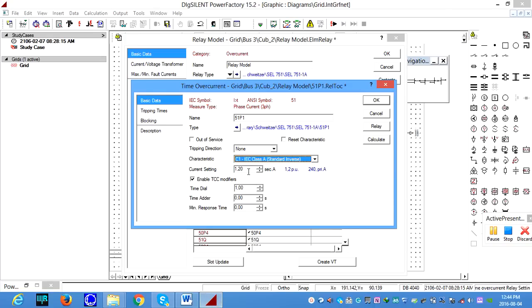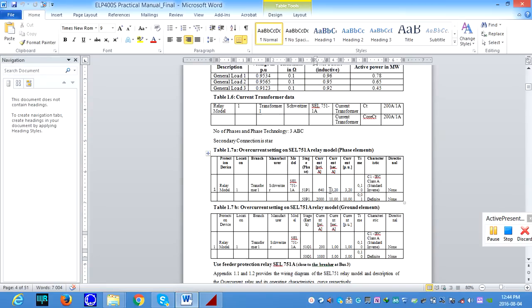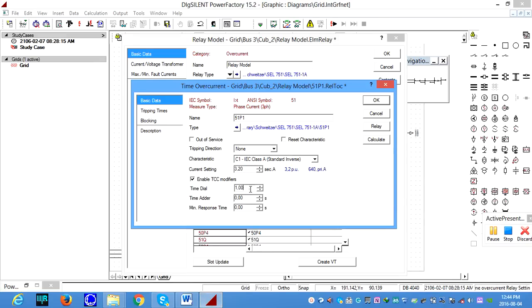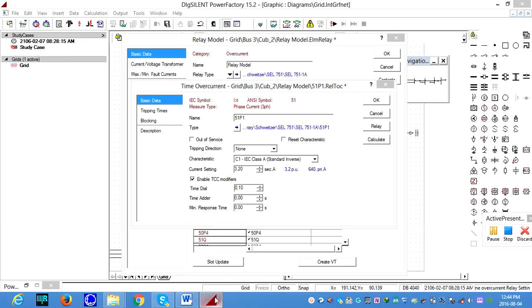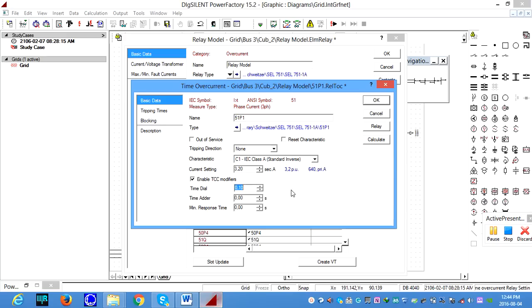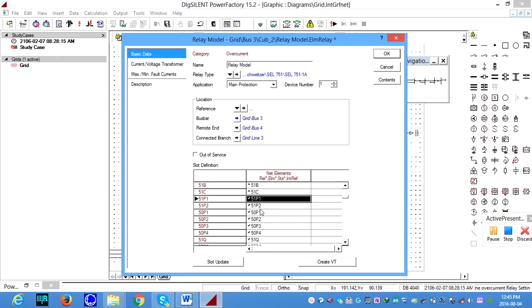Okay, and the time setting, we need to make sure of the time dial and the current setting. The current setting in this case we're making 3.20. Okay, if you look at the manual here, 3.20, the current setting on the secondary side. Okay, so secondary amps, and the time dial setting is going to be 0.10. You can see here the time dial setting is 0.10. Okay, we are happy about that. IEC standard inverse, 3.20 and 0.10.